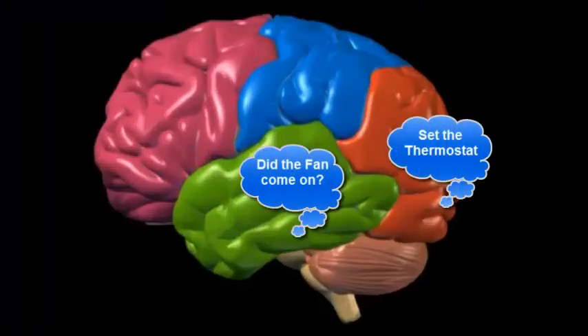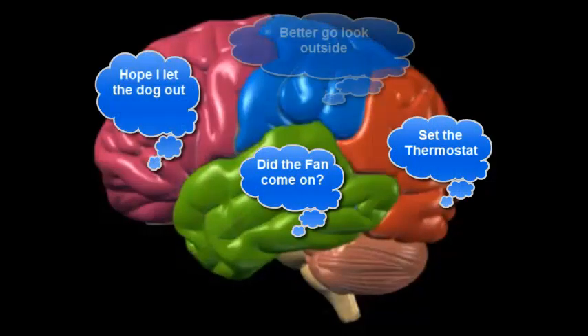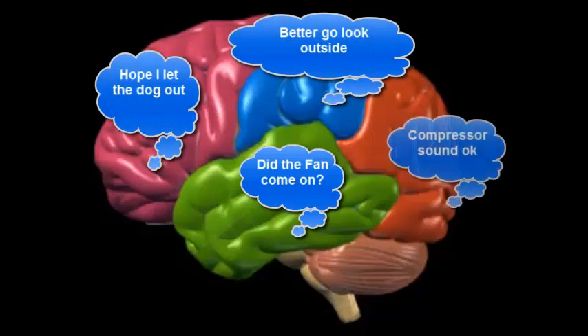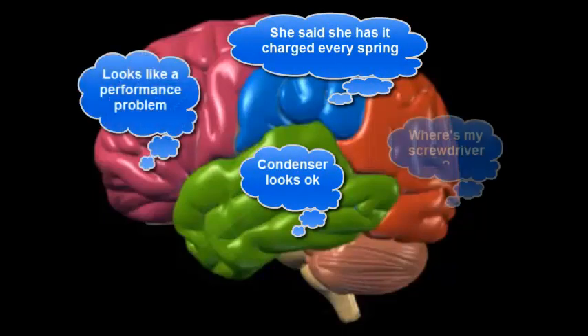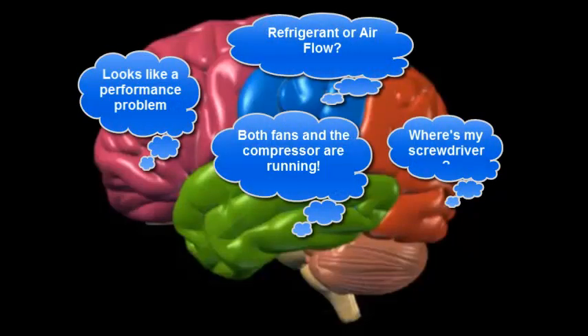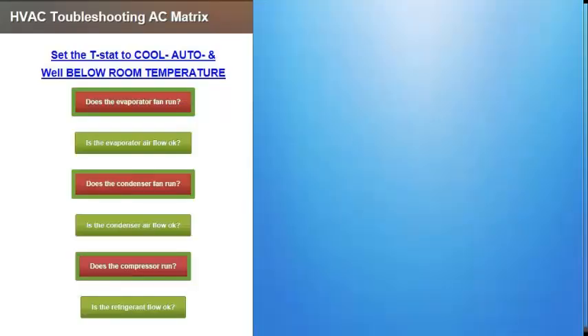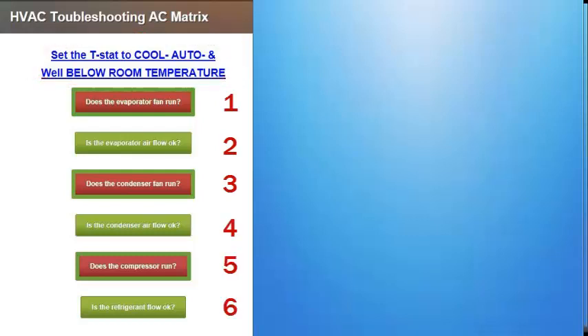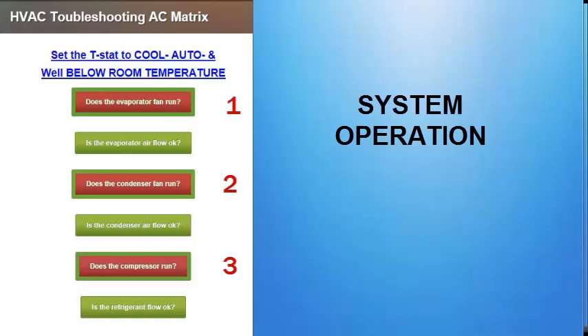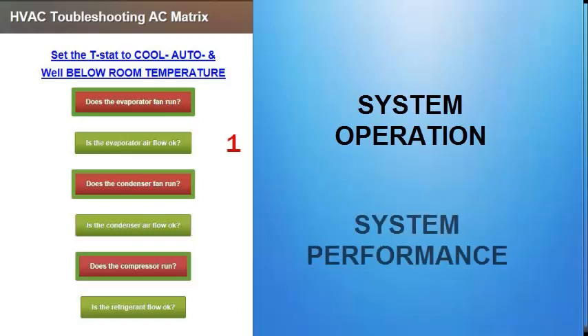If it were possible to hear everything that goes on inside a technician's brain during diagnostics, we would quickly discover that successful technicians carry with them a mental roadmap of the basic diagnostic process. They are constantly looking and listening for clues that will lead them to system problems as quickly and directly as possible. Once the technician sets the thermostat to cool, auto, and well below room temperature, successful technicians begin by asking themselves six very basic questions — three questions about system operation, and three questions about system performance.